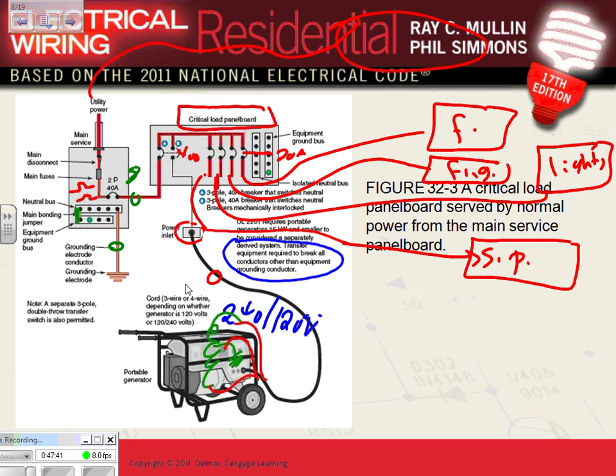Any question about this? So we're running 3-pole 40A switches, neutral. And if you look at this here, I don't know if you can read this, very important, guys. That's you switching the neutral. The reason why we switch the neutral, everybody knows why we switch the neutral, because it's a separately derived system, is you switch the neutral as well as the hot. You do not want to depend on the neutral of the utility. That's what a separately derived system is. It has its own neutral. You run your own neutral.